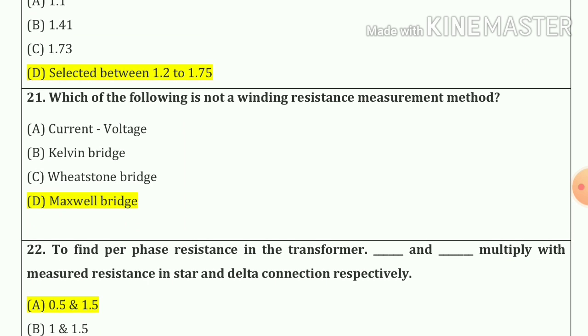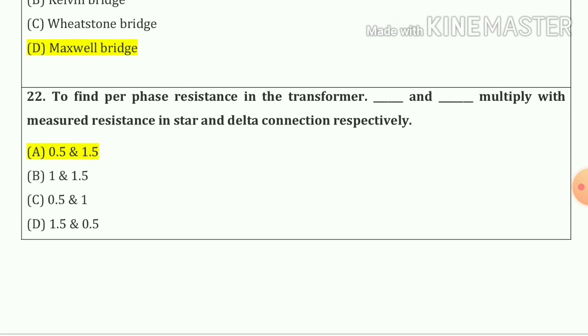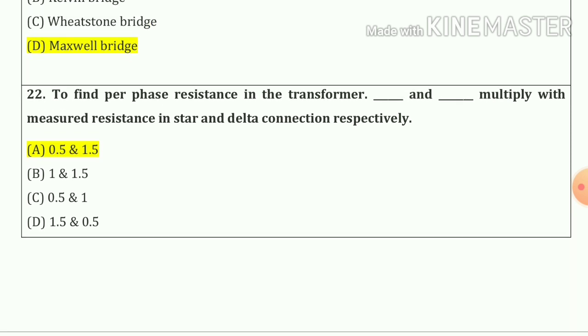Question number 21. Which of the following is not winding resistance measurement method? So our answer is Maxwell bridge. Question number 22. To find per phase resistance in the transformer, 0.5 and 1.5 multiply with the measure resistance in star and delta connection respectively. So 0.5 for the star and 1.5 for the delta connections.